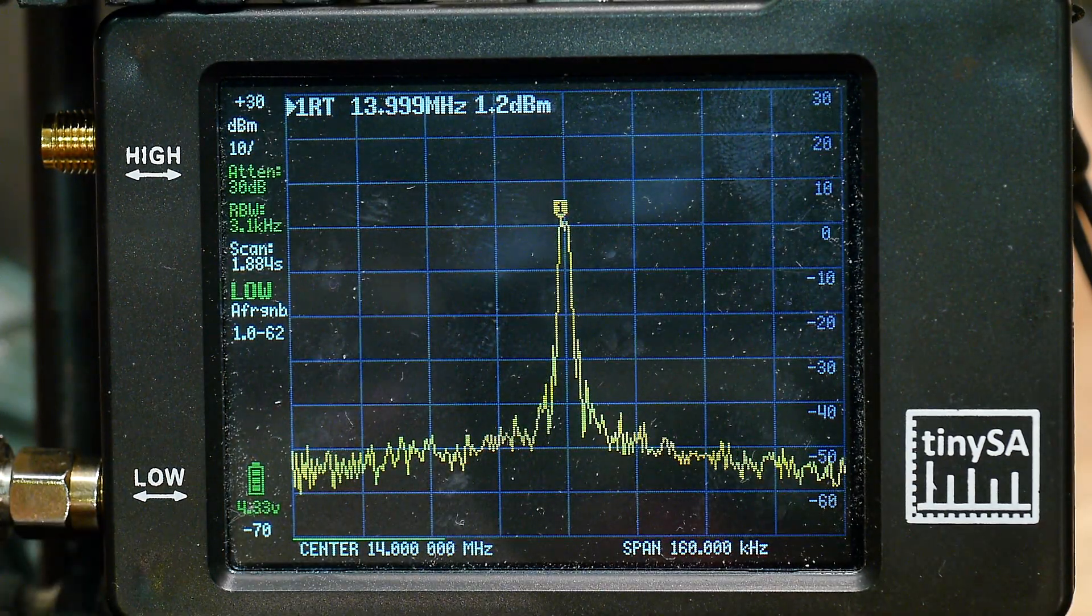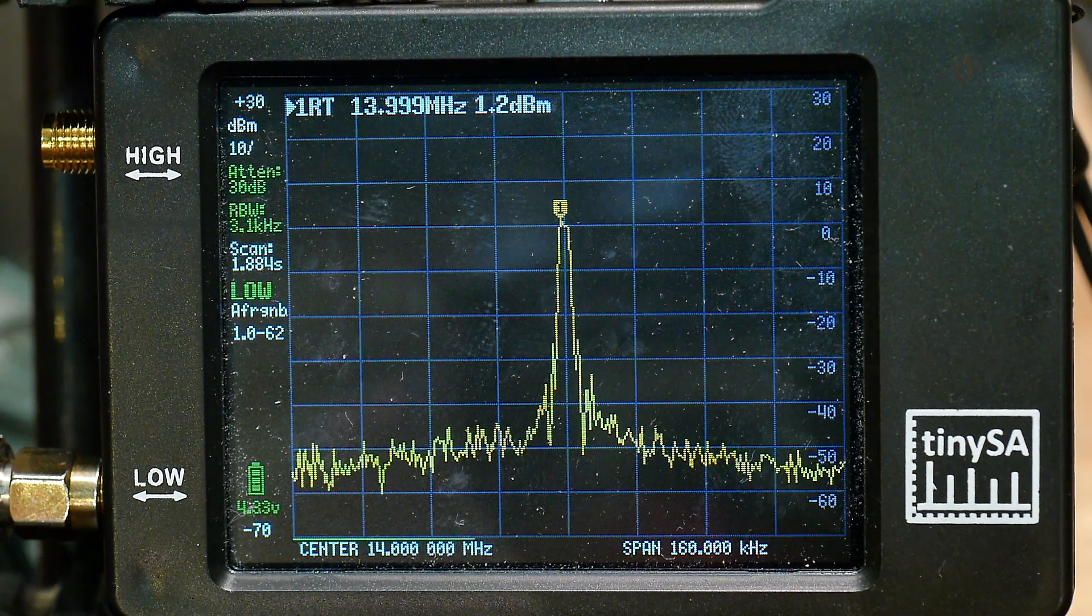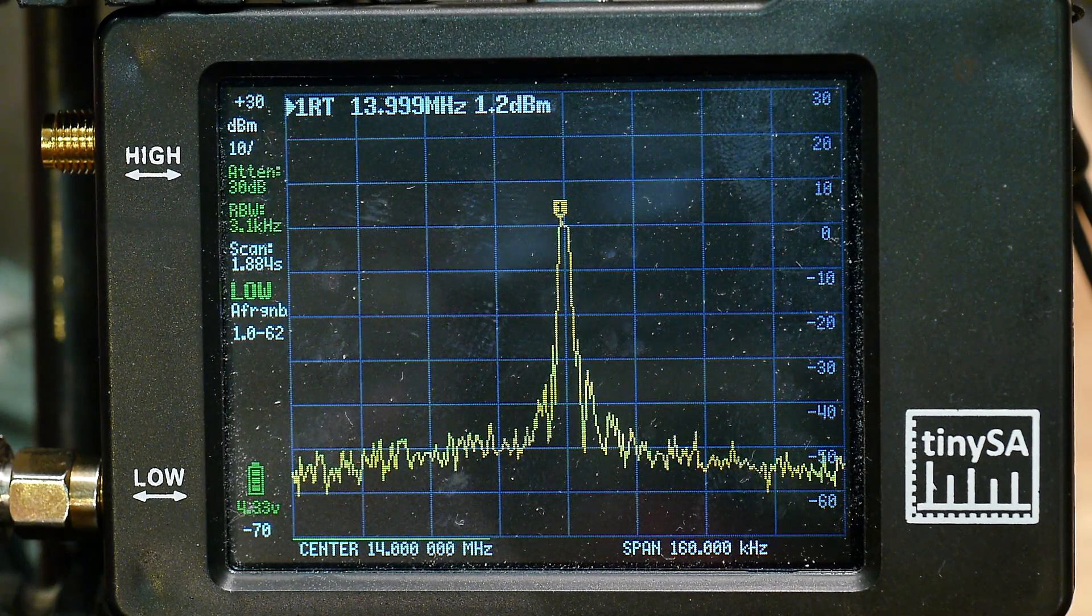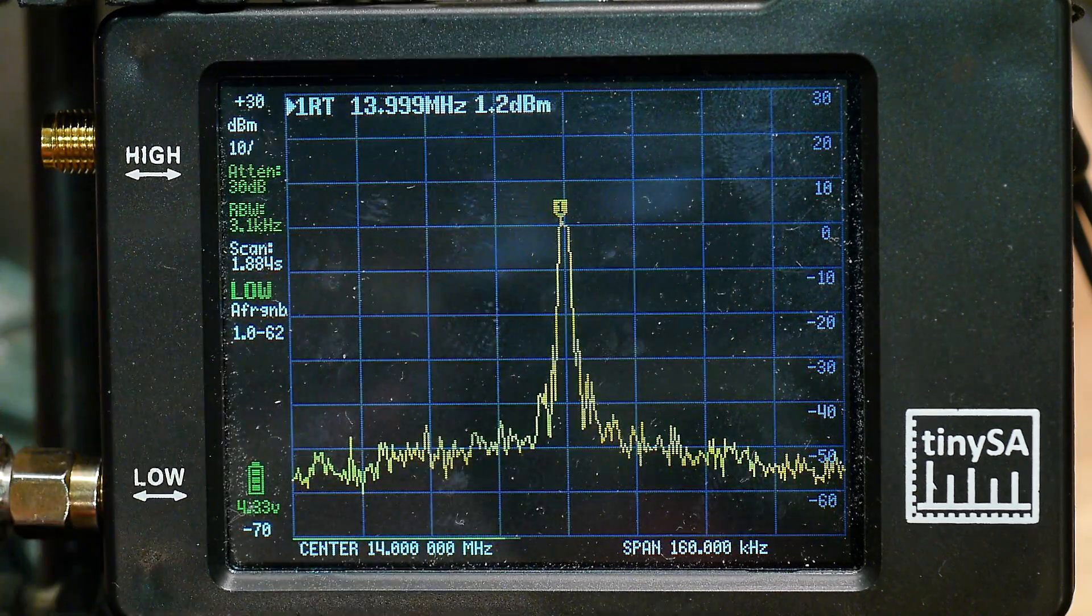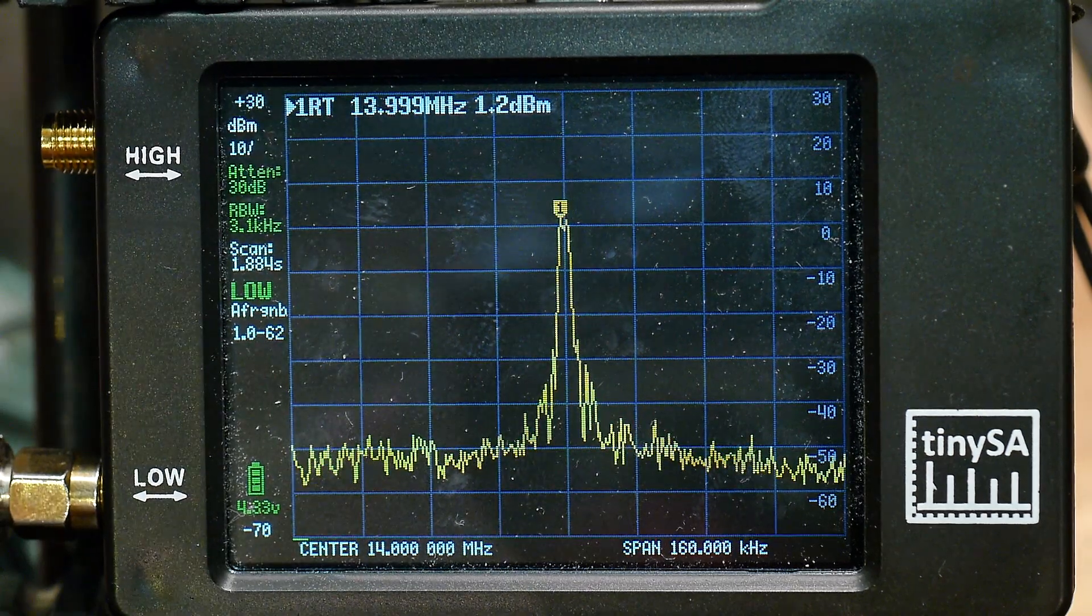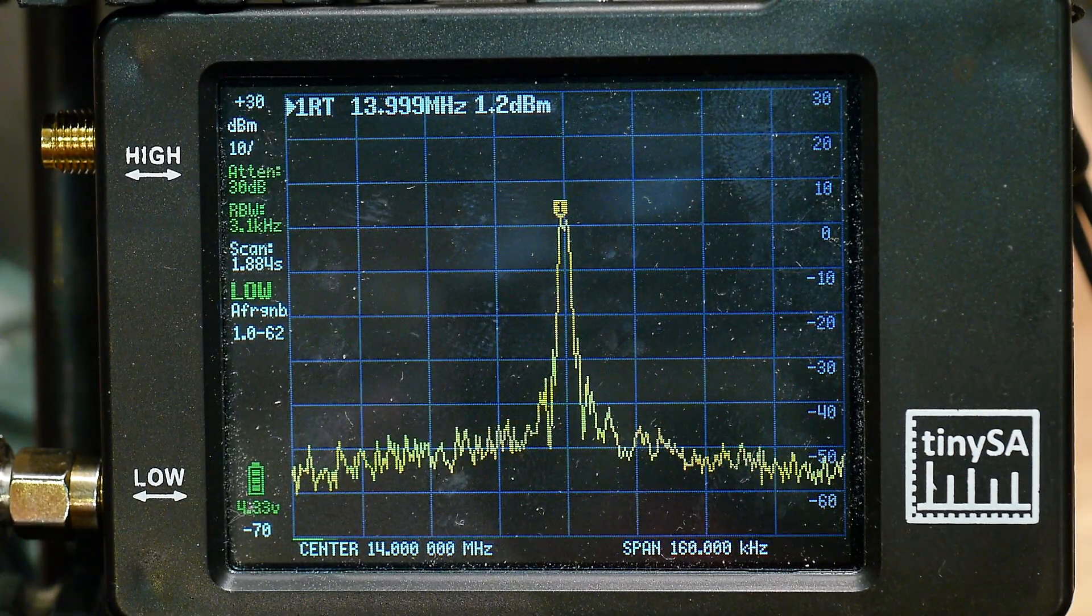We know we have a 0 dBm signal so we're going to attenuate it below minus 30. You always want to be looking at signals below minus 30 dBm. So either use an external attenuator to drop it down or use the internal one. Now the internal one only goes to 30 so we've maxed out here. But we have a better looking display now.